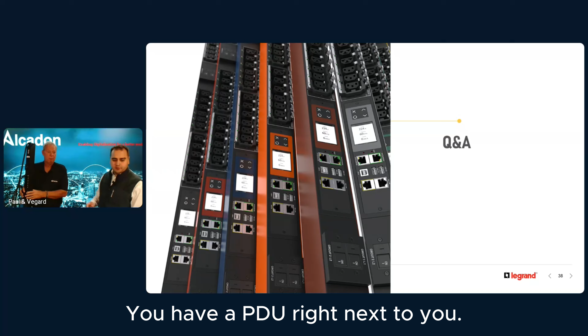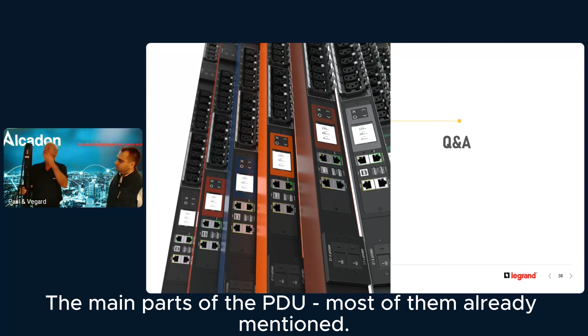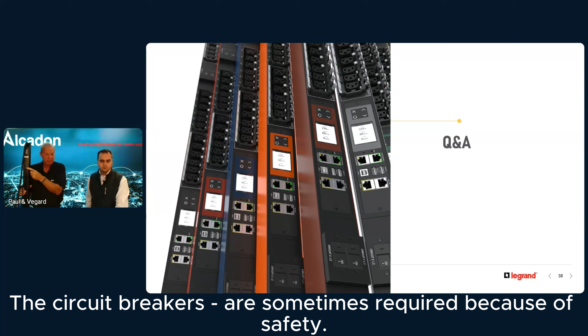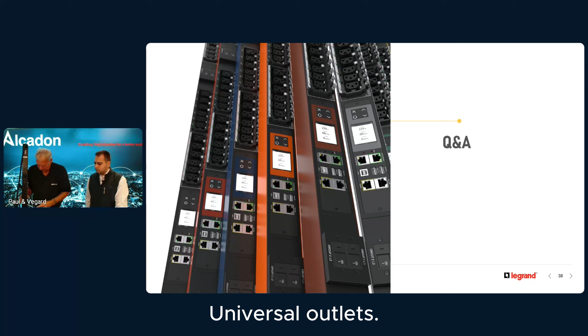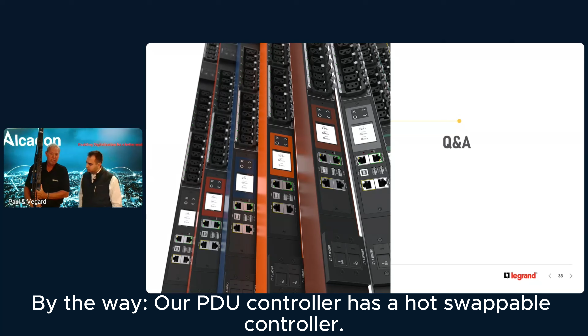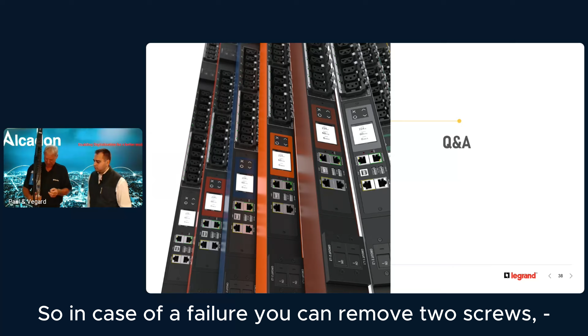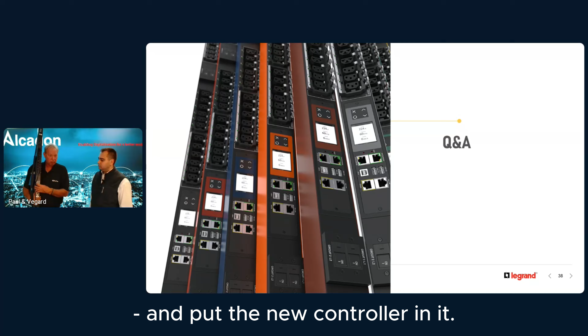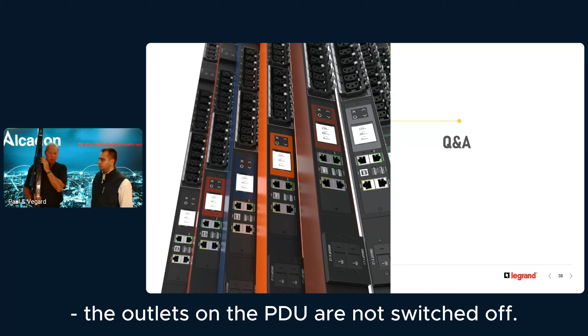You have a PDU right next to you now - can you walk us through the main parts of the PDU? Most of them I already mentioned: the input cord on the input side, circuit breakers which are sometimes required for safety, the outlets, universal outlets, and the controller. Our PDU controller is hot swappable, so in case of failure you can remove two screws, take out the controller, and put a new one in - and the outlets on the PDU are not switched off when you do this.